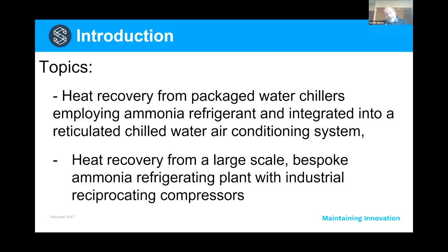So two examples. One is from an existing installation that was commissioned about 10 years ago: two package water chillers air conditioning a public administration building south of Brisbane. The chillers use ammonia refrigerant, and a little desuperheater is fitted to these chillers to produce domestic hot water. The other is a very large plant, a 500,000 cubic meter cold store, where we fitted a desuperheater to the common discharge pipe out of the ammonia compressors to recover some high grade heat that's used for a number of purposes in the plant.